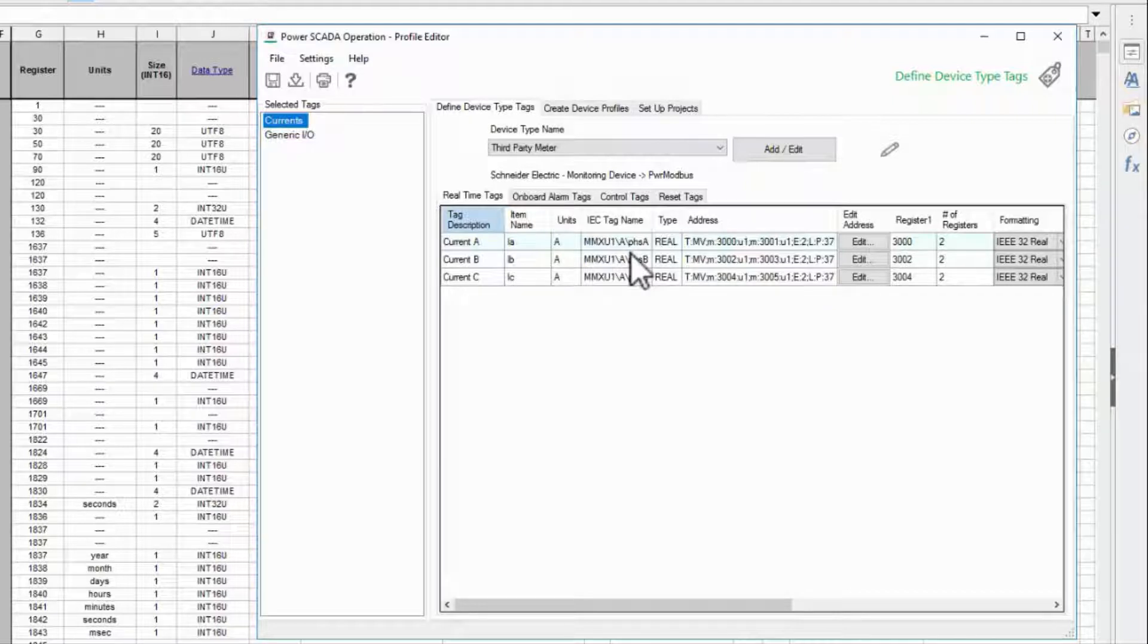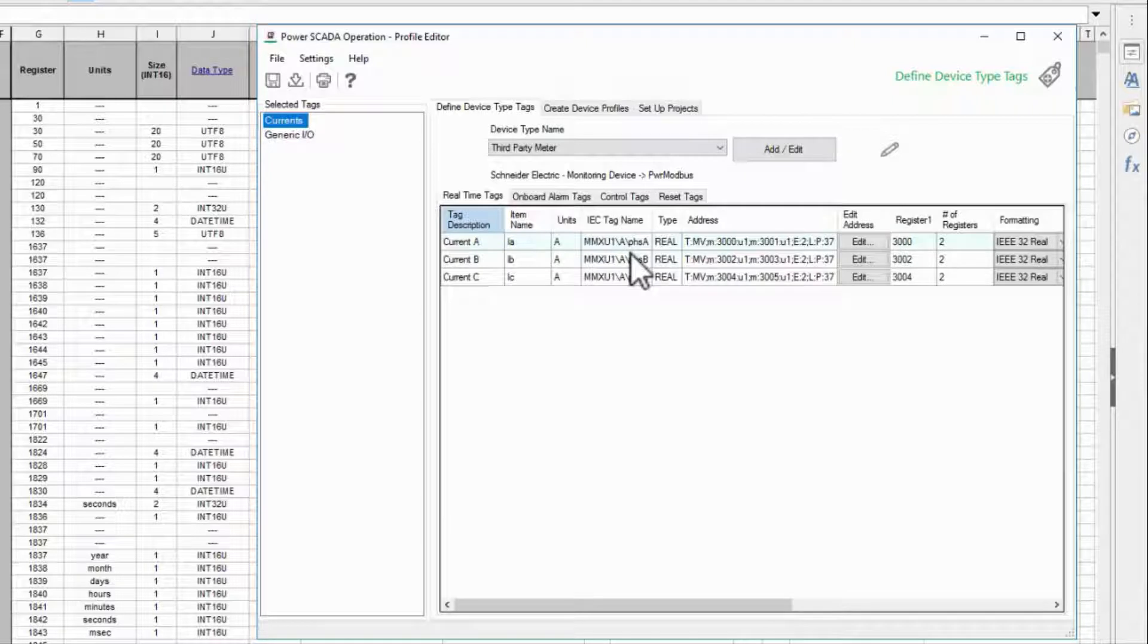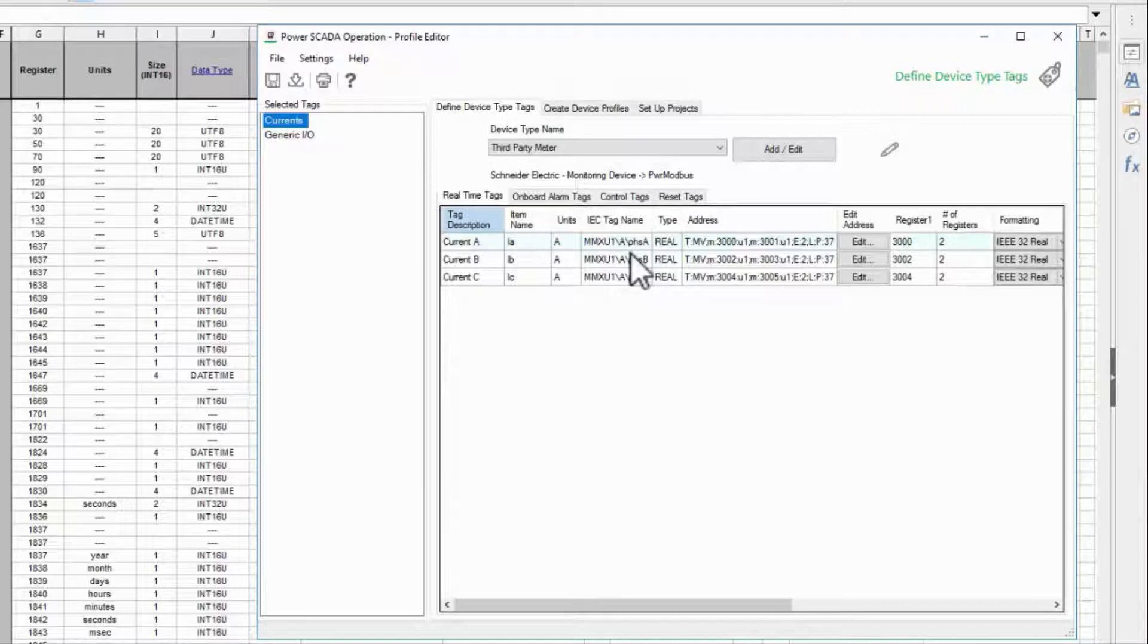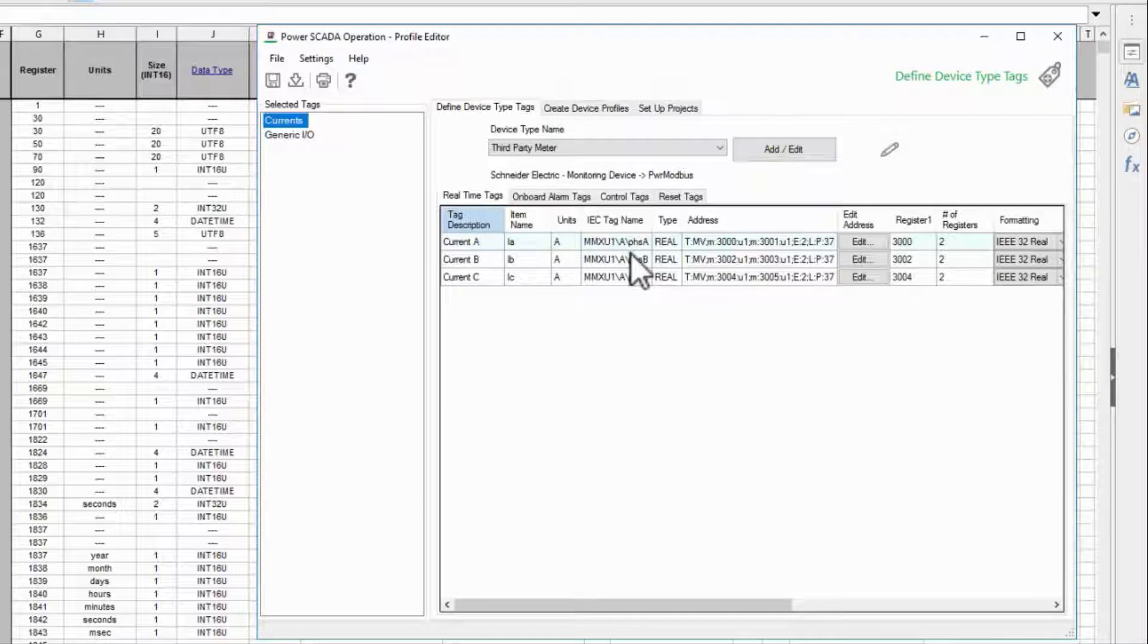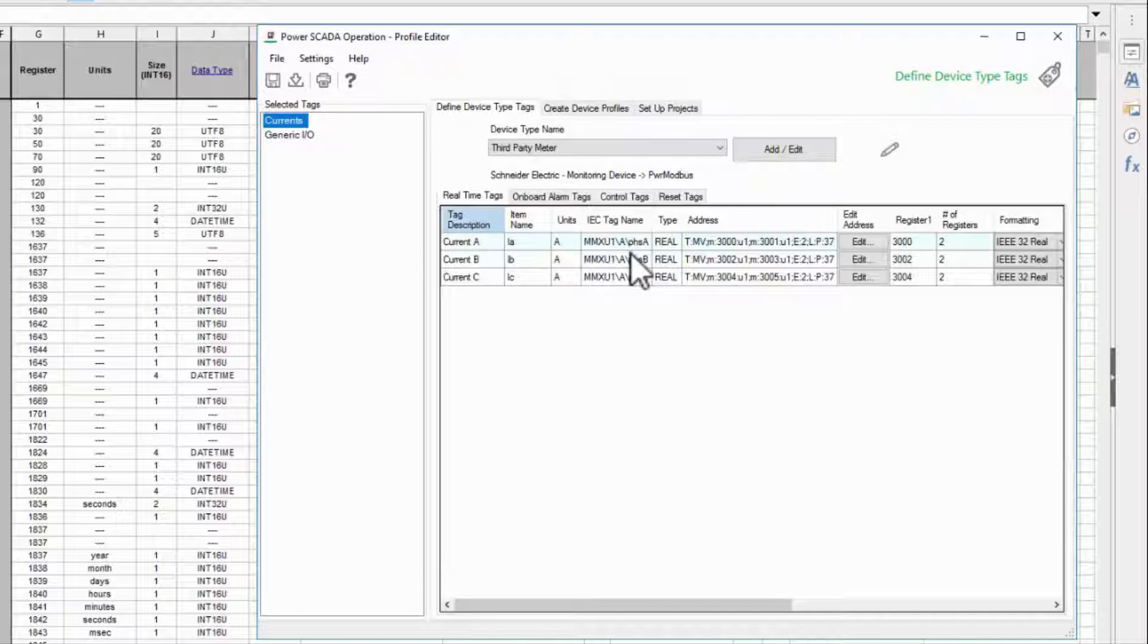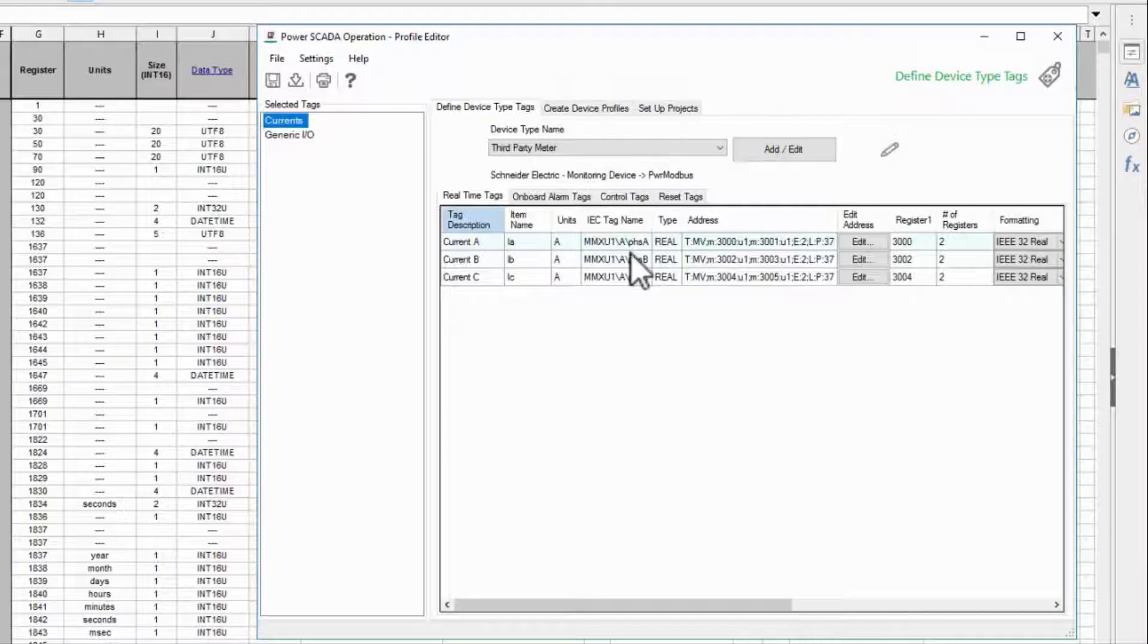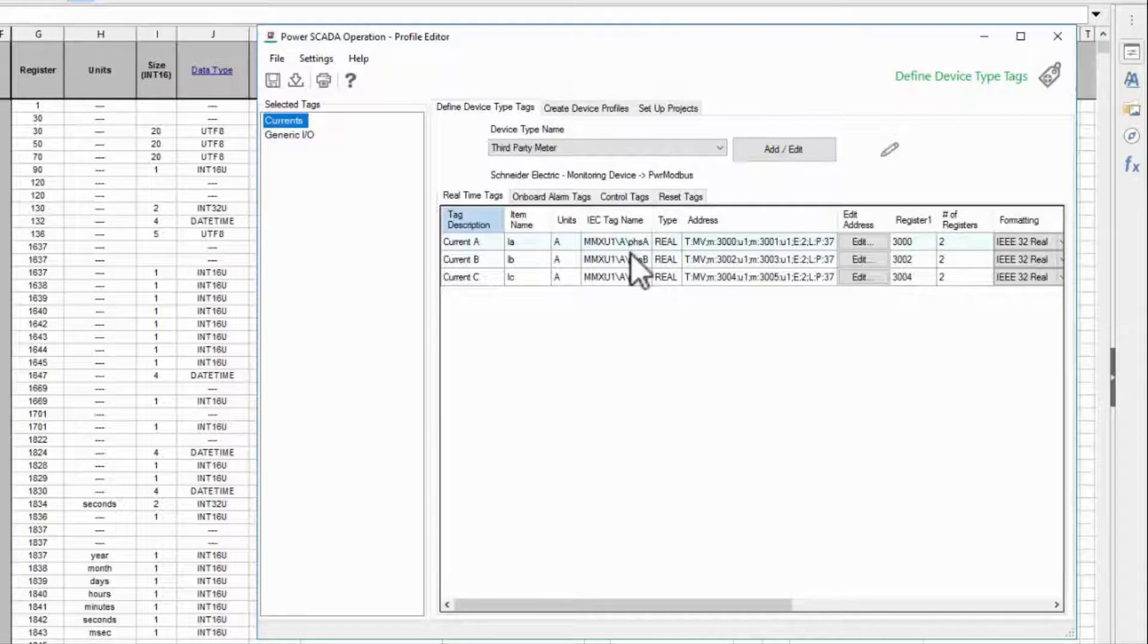While it's not absolutely necessary to follow this convention, you should at least come up with a naming standard. A standard will allow you to use common code for different types of devices. If my phase A current is always MMXU1/A/PHSA, I can write code that operates on current for all my electrical meters. If you're interested in following this standard, I encourage you to read up more on IEC 61850.